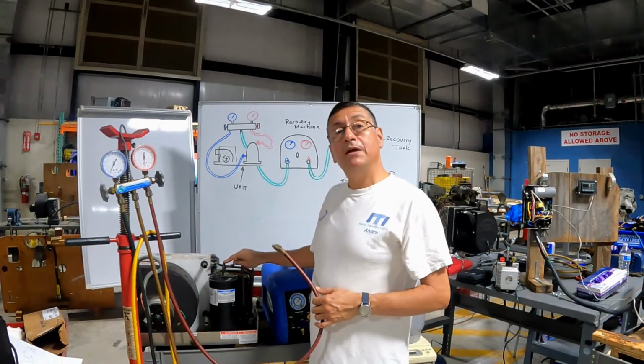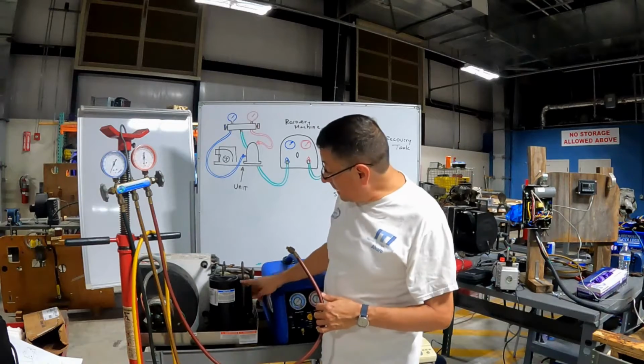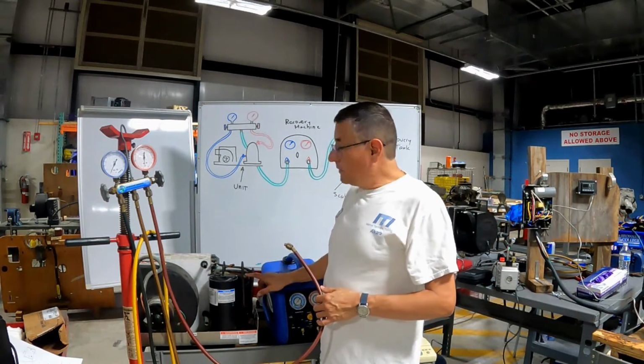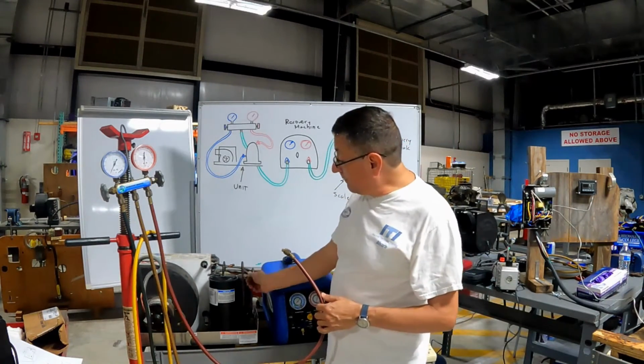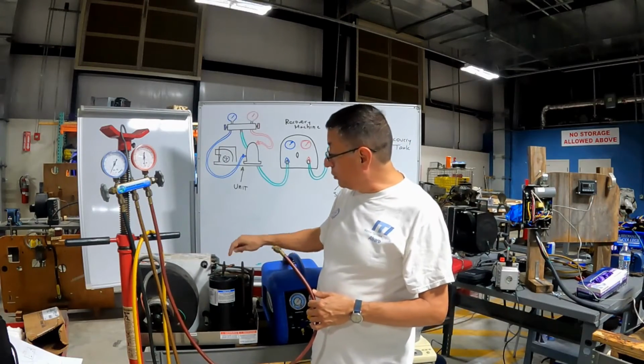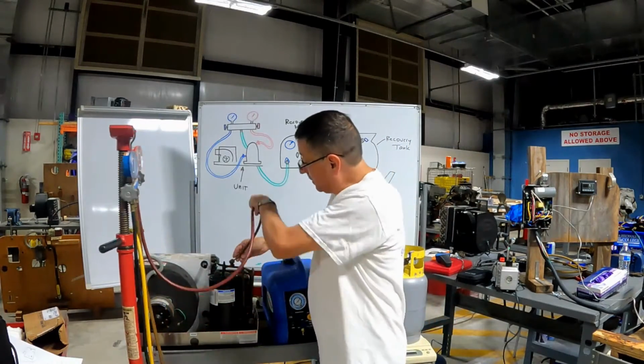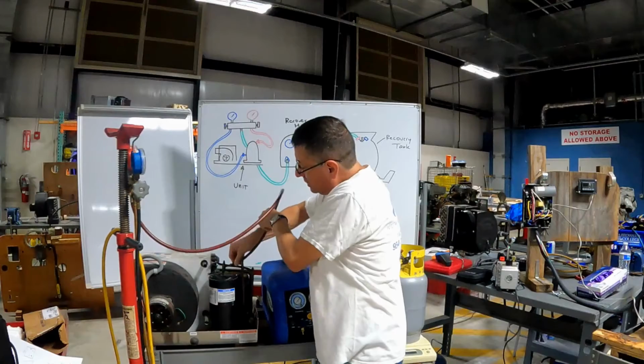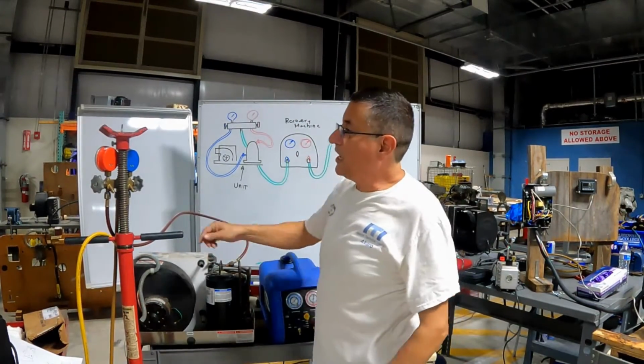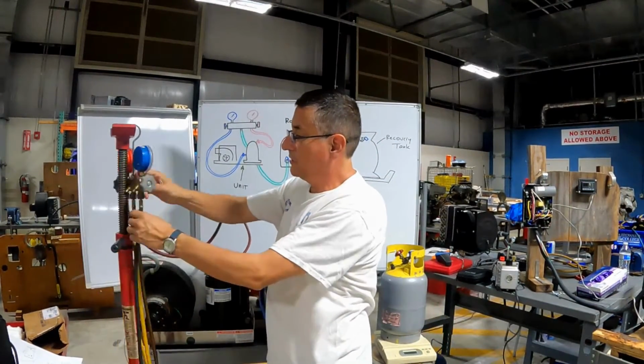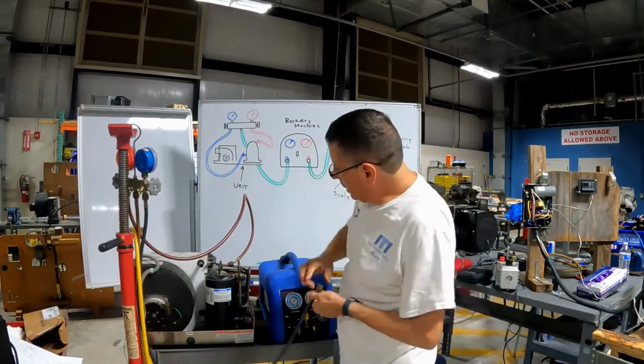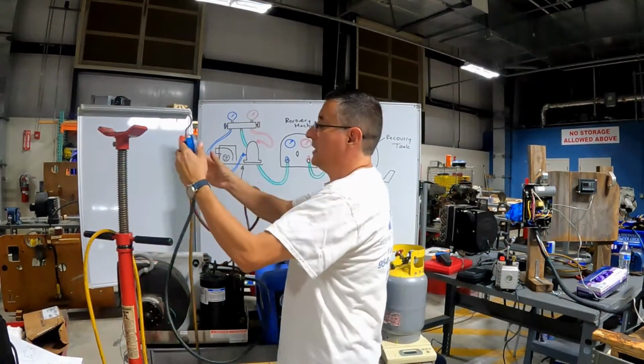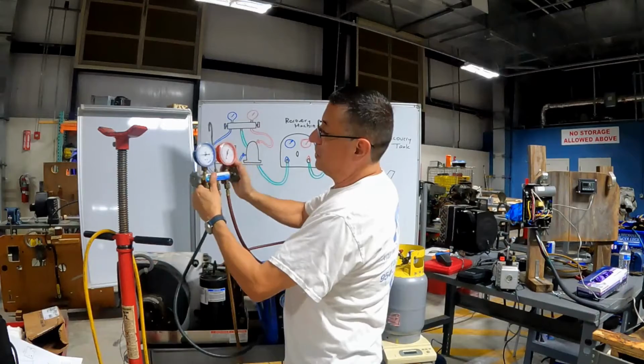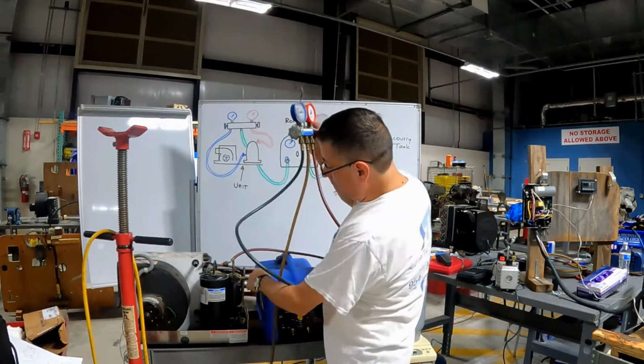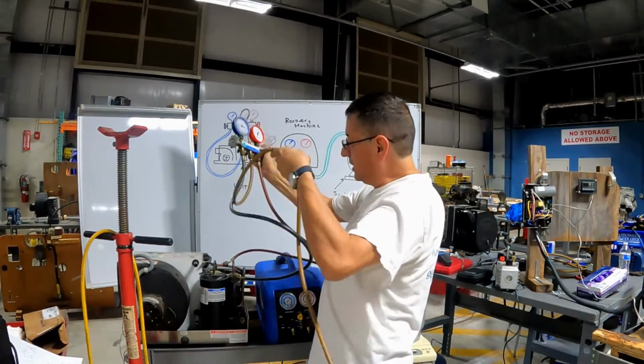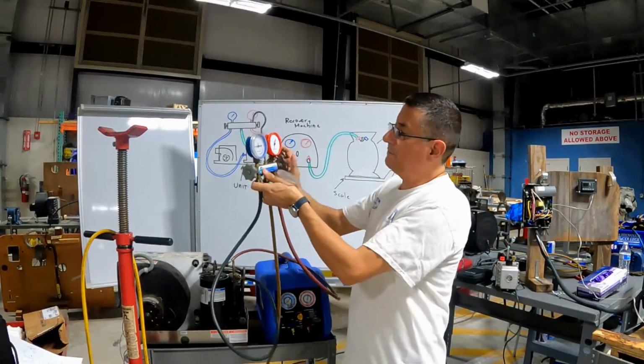Normally the smaller pipe is for high pressure and the bigger pipe is for low pressure. In the majority of the equipment you have caps with the blue color or red color. This is the red, this is for high pressure, and we are going to insert the red one in the high pressure, the blue one in the low pressure side. Try to keep the valves completely closed.